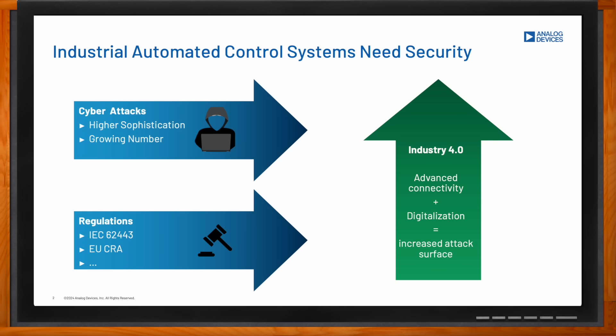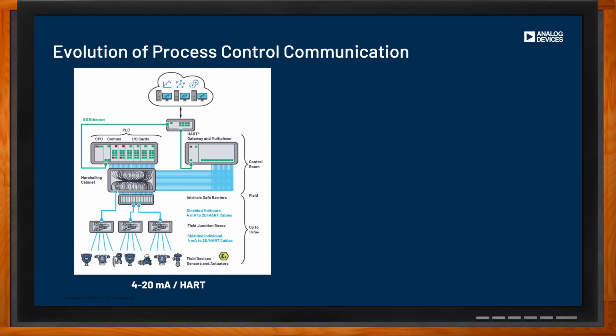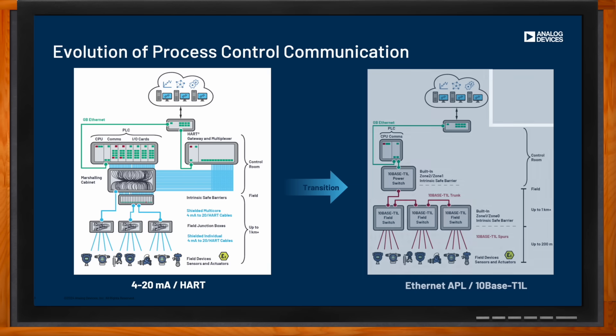We've talked about process control communication a couple of times here on Chalk Talk, and there has been quite a bit of evolution in this space. In the past, people would use traditional communication media such as the 4–20 milliamp current loop and HART protocols. Today the industry is moving to more advanced connectivity media such as Ethernet APL, or 10BASE-T1L, which is a single-pair Ethernet — opening more possibilities and flexibility in communication.